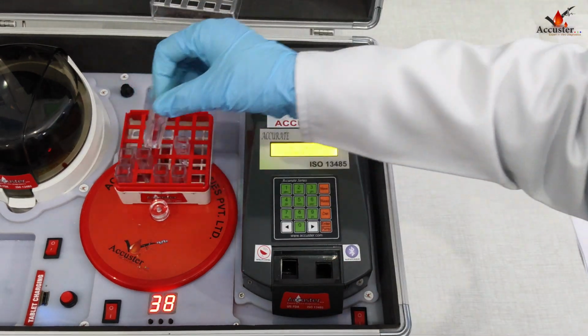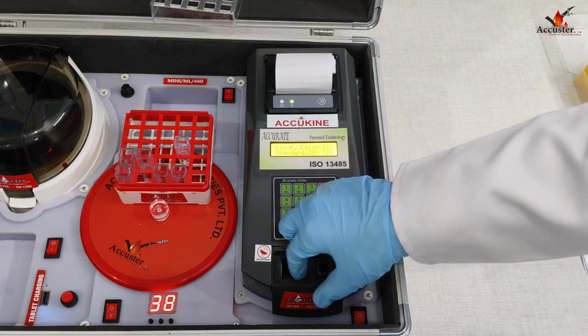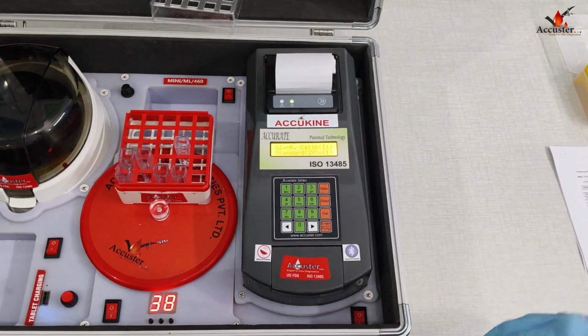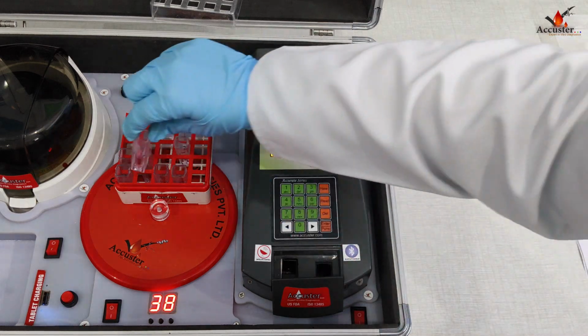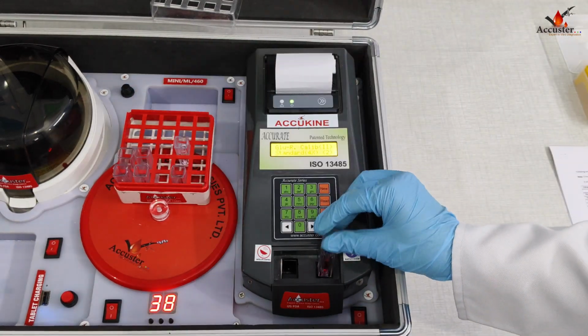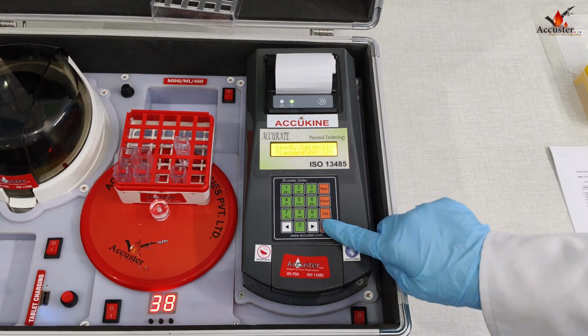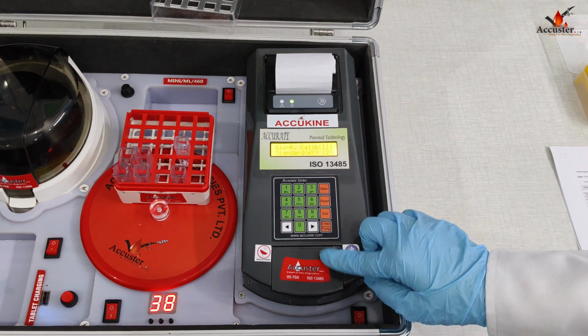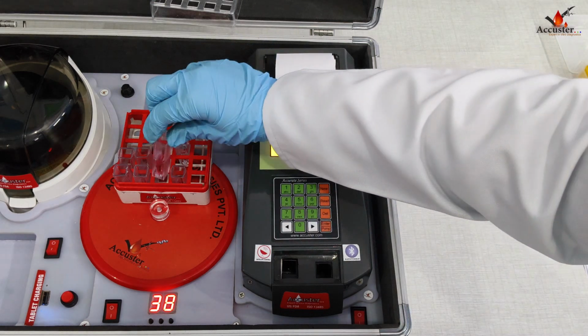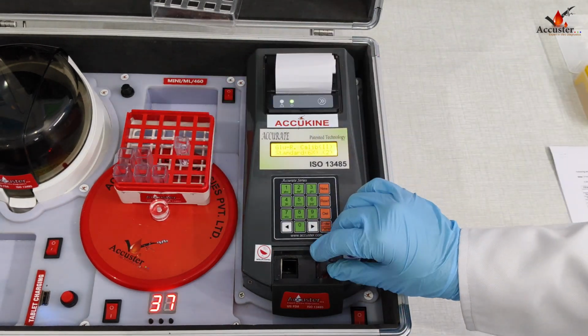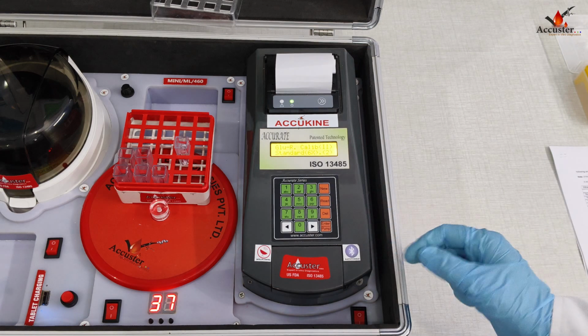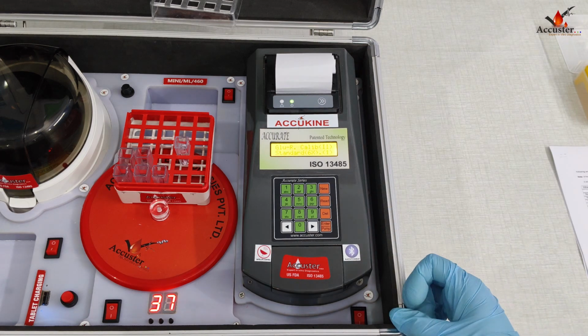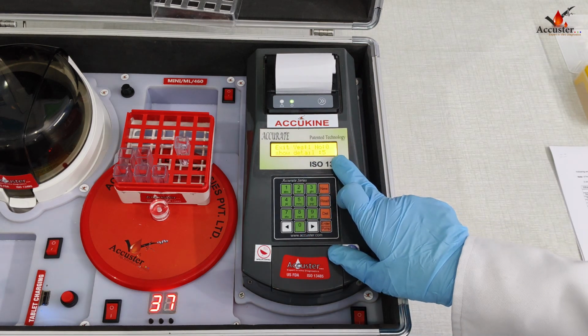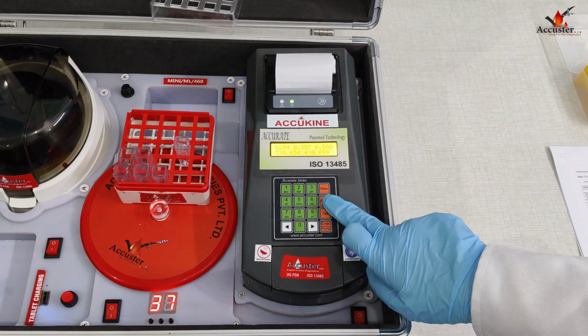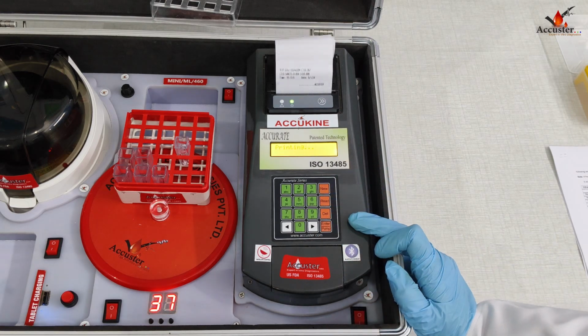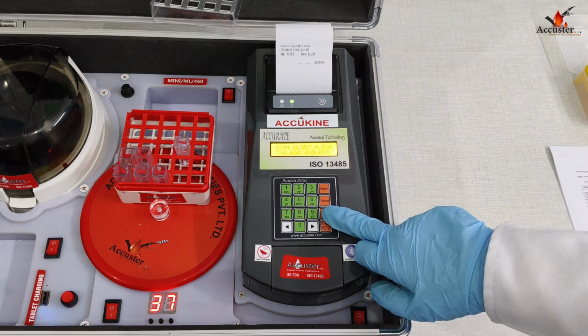For 2x, insert the cuvette labeled as 2x and then press enter. For 4x, insert the cuvette labeled as 4x and press enter. For 6x, insert the cuvette labeled as 6x and press enter. Now the calibration is done. To view the value on the display, press 5. To print, press read. Then press del button and yes to go back.